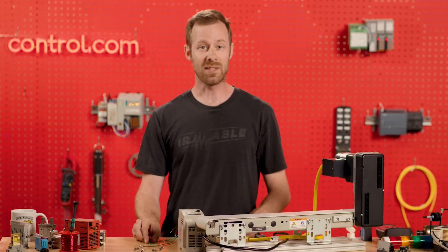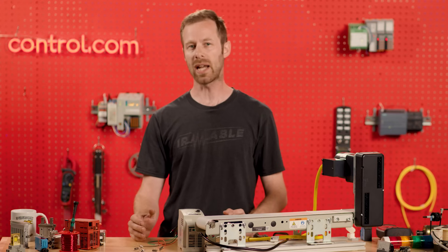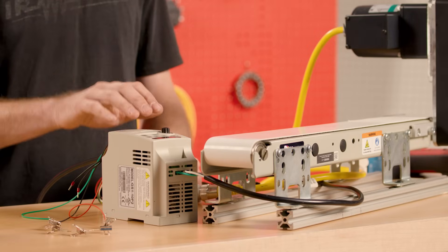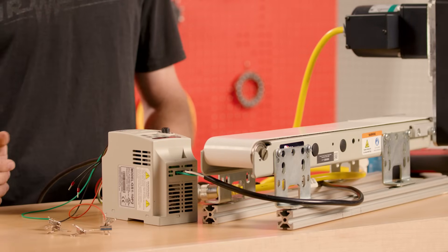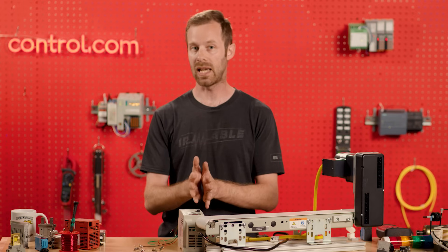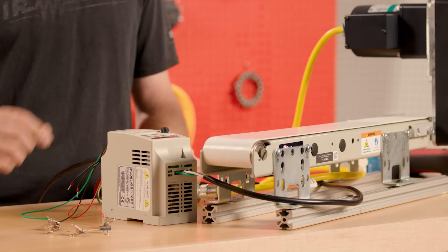Incredible technological breakthroughs are made possible largely by a curious mind and education. In this spirit, we bring you David's Corner. For some simple variable frequency applications, we don't need network control that determines the speed of the motor, but we do want better control than just on and off. So in those cases, we often turn to the potentiometer — this variable resistance device built right onto the front of the VFD — very convenient for adjusting the speed. The problem is, sometimes these things are closed inside a control cabinet, and without opening the cabinet and giving somebody access to the front of the VFD, controlling that speed for fine-tuning might be difficult. So instead, we can use the analog input and change a parameter that says to look at the analog input to get your speed command reference, not the network port and not the preset potentiometer built right into the front. But let's explain a little bit more about these potentiometers and what that means.